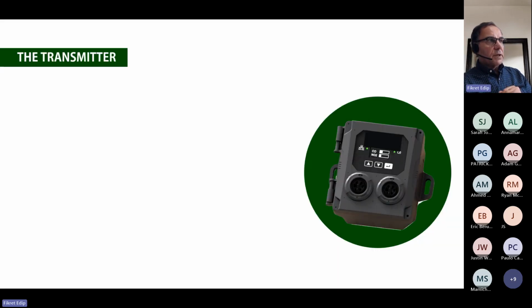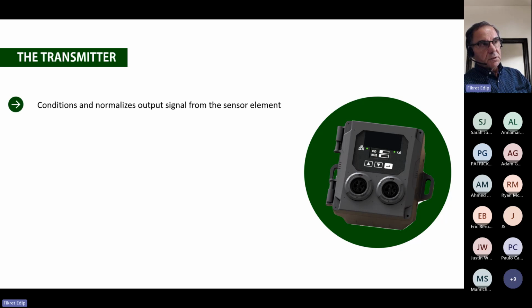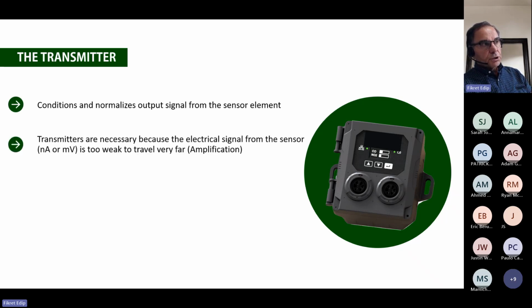Now, once we have all that put together, we'll begin with the transmitters. Transmitters, what do they do? They transmit a signal to the controller, and they have a built-in sensor element. There's a miswording here. A lot of people say, I want to get a sensor. Well, the sensor is a sensor element which is inside the transmitter. A transmitter, with the box and the circuit board and the sensor element all together, becomes a transmitter that transmits a signal to a controller.